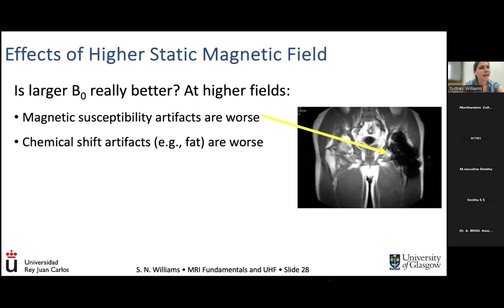It also will have effects at higher field strength of things called chemical shift artifacts, which is essentially when macromolecules like fat or lipid again cause slightly different resonance. That Larmor frequency is slightly different for the fat compared to water, and it'll cause those types of tissue in the body to have a shift and appear in almost the wrong location of the MRI image. And then, while generally implants that are put into people nowadays are non-ferromagnetic and generally MRI safe, they might only be approved conditionally for lower magnetic field strength. And so perhaps you might not be able to scan someone with, for example, a 7 Tesla MRI if they have certain types of implants. So maybe there are some challenges associated already we can imagine at the higher magnetic fields.